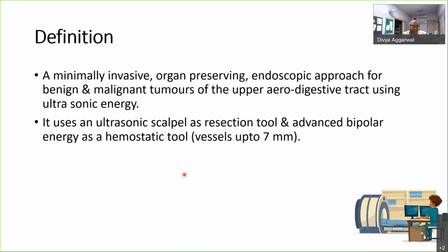So two energies are used in TOUSS. One is the ultrasonic scalpel, the ultrasonic energy, and another is the advanced bipolar energy. The combination of the two helps you to cut the tissue and to seal the vessels, to do hemostasis. And mind you, vessels up to 7 mm can be controlled with this advanced bipolar energy system. So mind you, the advanced bipolar energy is the bipolar that we generally use. It is not ultrasonic. The ultrasonic scalpel is the other component.